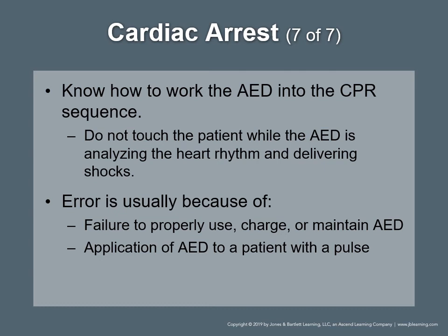Automated external defibrillator maintenance. Become familiar with the maintenance procedures required for the AED. Read the operator's manual. An error is usually because of failure to charge or maintain the AED, failure to use the AED correctly, or application of an AED to a patient who has a pulse. If the AED fails while you are caring for a patient, report the problem to the manufacturer and the U.S. Food and Drug Administration.